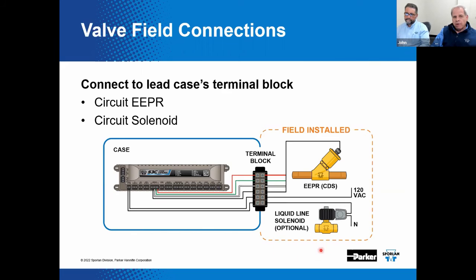And you would have 120 volts. We're saying 120 volts because the design supports that voltage as opposed to others. And you've got the liquid line solenoid valve being wired, and then the termination points for the EEPR here on the terminal block. And then we show their corresponding landing spots on the S3C case control over here. Makes sense, right?